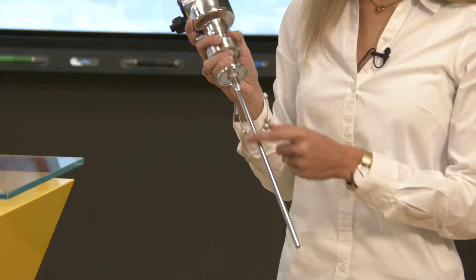So we have here the probe, it's the guided wave radar. Here we have the media which is in contact with the probe, and then we have the electronics. And for the autoclaving process, you can disassemble the electronics because the electronics cannot withstand such high temperature and also the pressure. Here we have a blind plug which protects the electrical connection, and like this you can have the complete skid including the probe mounted, and then put it into the autoclaving process for the actual cleaning. And afterwards, of course, the electronics is installed again, and it starts all over again.